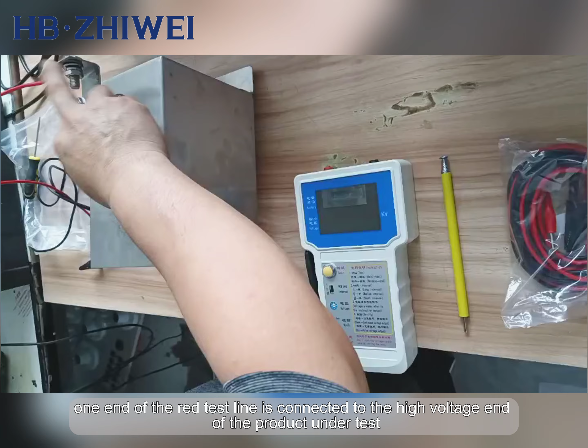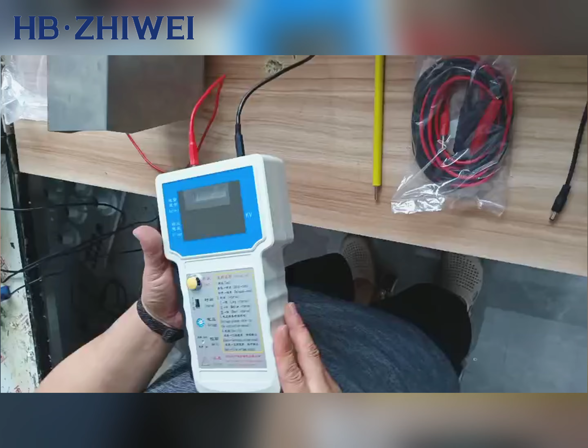Next, we will introduce how to use the device. One end of the red test line is connected to the high voltage end of the product under test, and the other end is connected to the red port on the top of the device. One end of the black test line is connected to the black port on the top of the device, and the other end is connected to the ground terminal of the product under test. Turn on the bottom power switch.